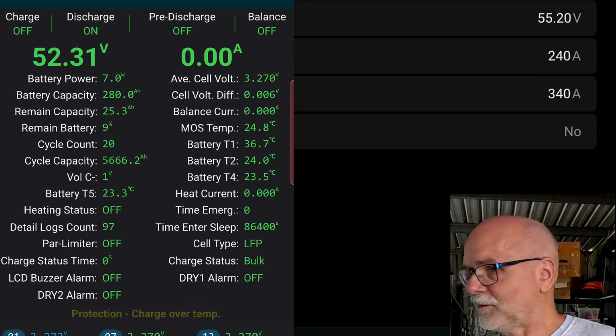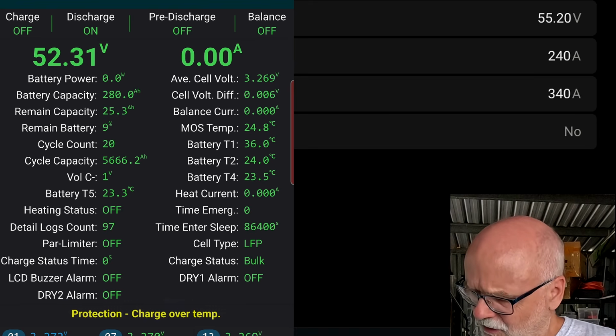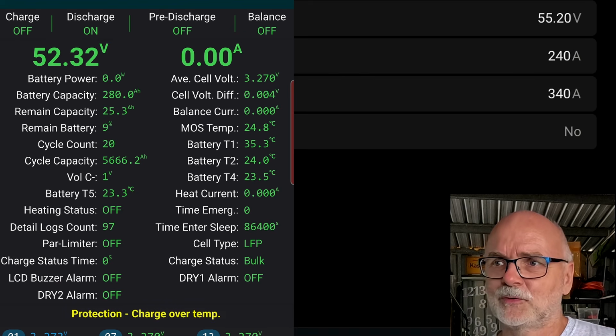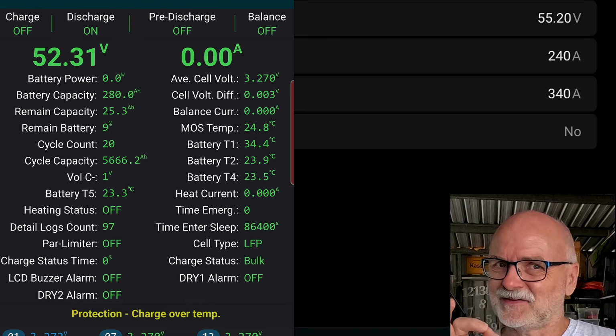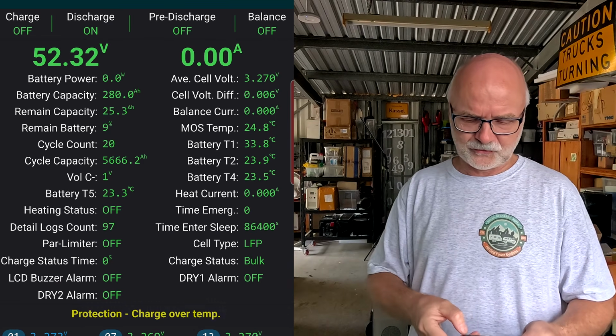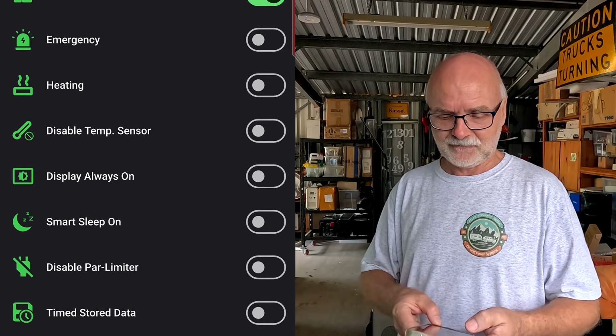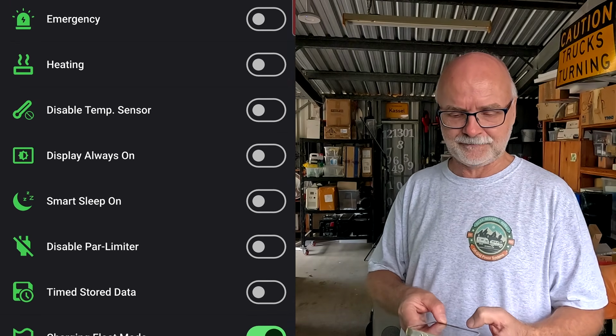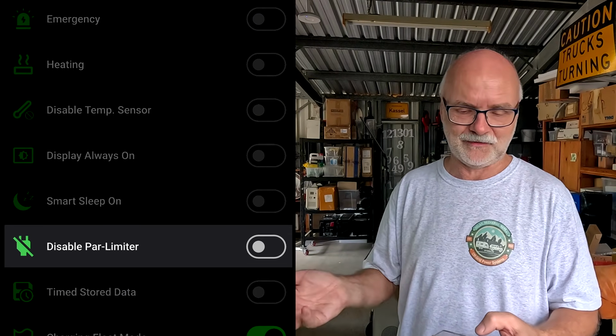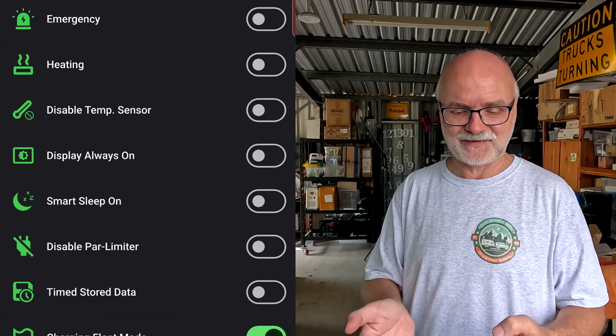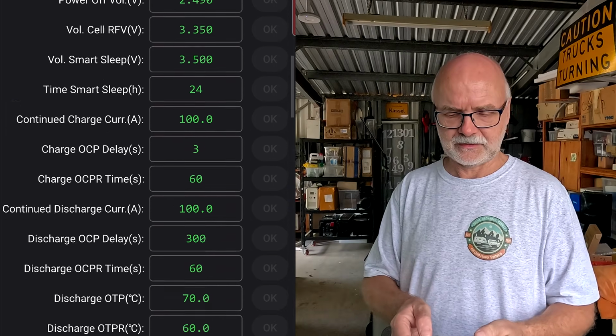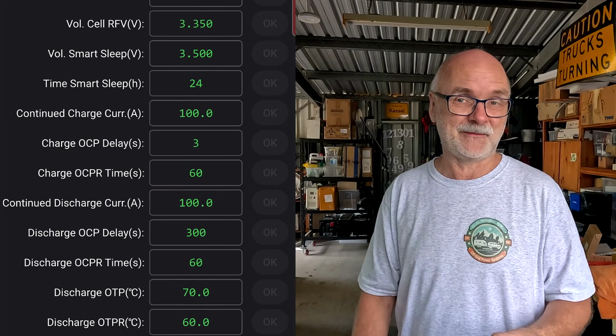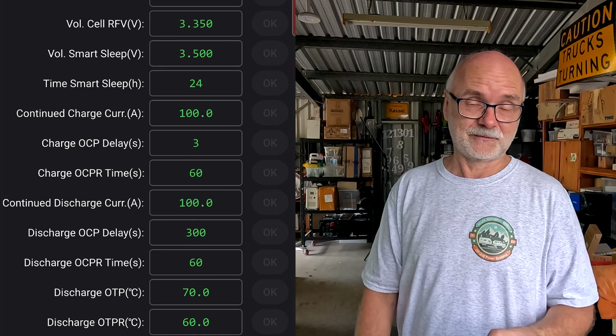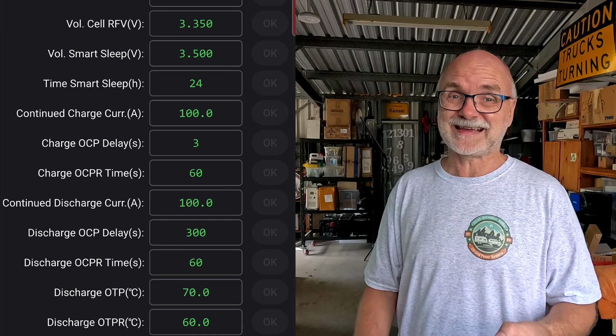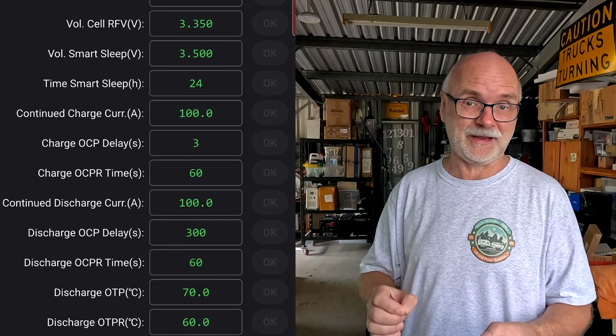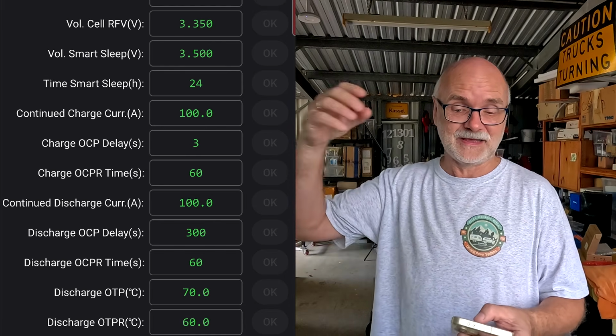Nice. Okay, while we have this battery open there, we probably can trigger an overcurrent protection as well, because here it is a bit tricky. If you go into the controls of your BMS, you have the ability to set the, it's called parallel limiter now. It's a current limiter. Yeah, and you can either disable it or enable it. It is enabled at the moment, and that means that if we go over 100 amps with this BMS here for 3 seconds, it would activate this current limiter and then reduce the current into this BMS to 10 amps only. Yeah, from over 100 amps down to 10 amps.